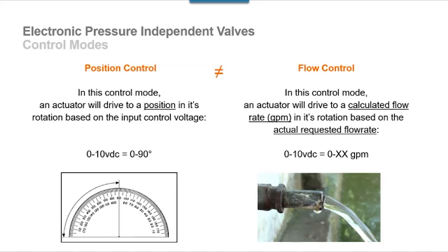With flow control, it's going to drive the actuator to the calculated flow rate in its rotation based on the actual requested flow rate. So let's say it's a linear valve. In my example, I had an 80 GPM valve. If it's linear and it gets a 50% signal, that valve is going to position to provide us 40 GPM of flow. Pressure independent takes into account that as pressure changes, the flow can change. Position control is just straight out: here's the physical position we want to drive the valve.